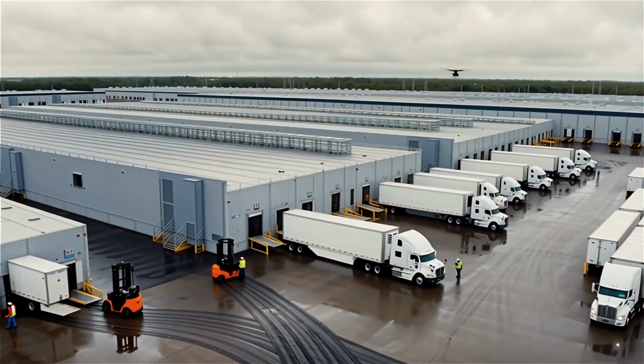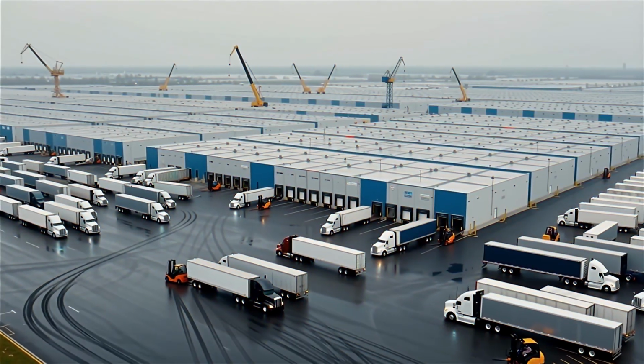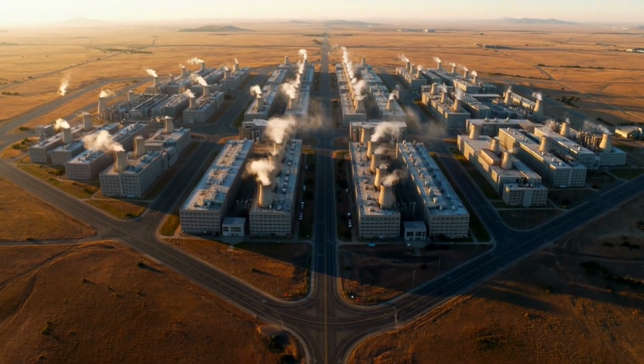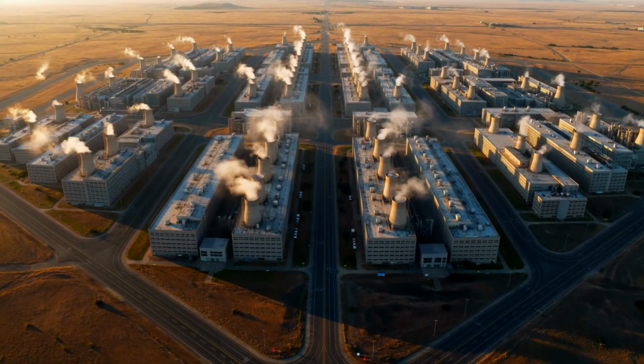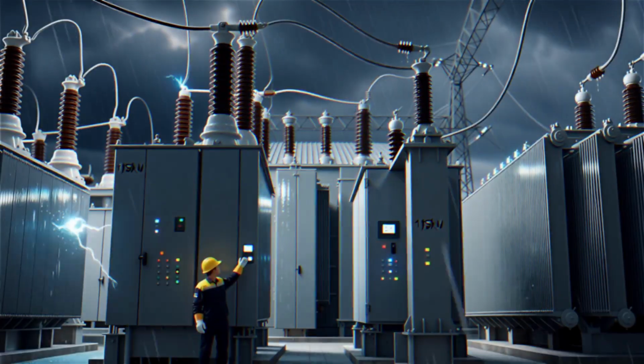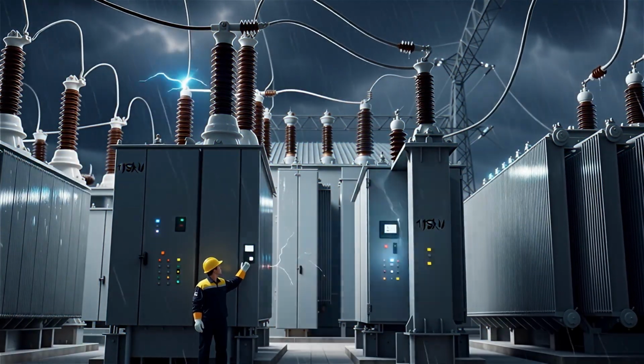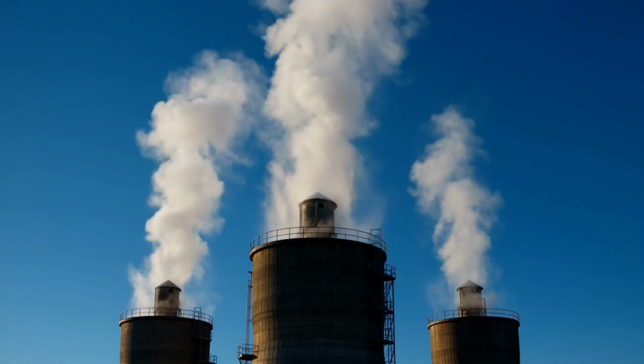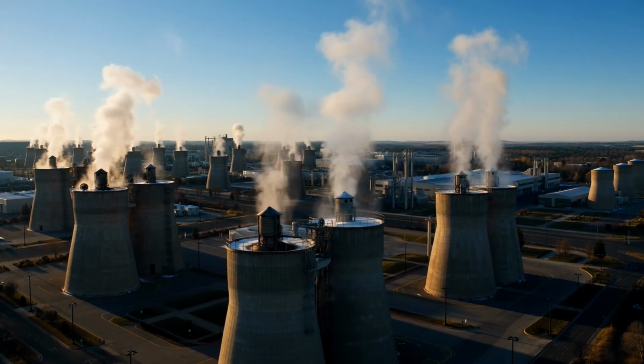But before a single server goes in, the facility needs its power infrastructure. And this is one of the most complex parts of the entire operation. Power arrives from the grid at high voltage, sometimes at 115,000 volts or more. It flows through massive transformer stations on the property, which step it down to voltages the building can distribute internally.